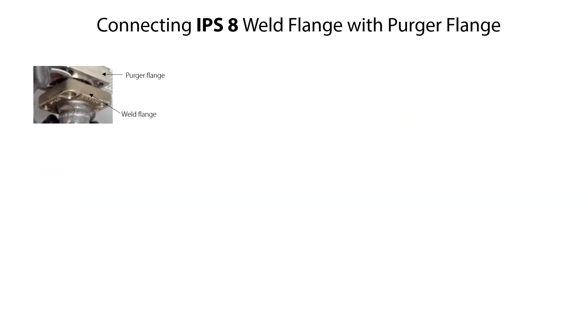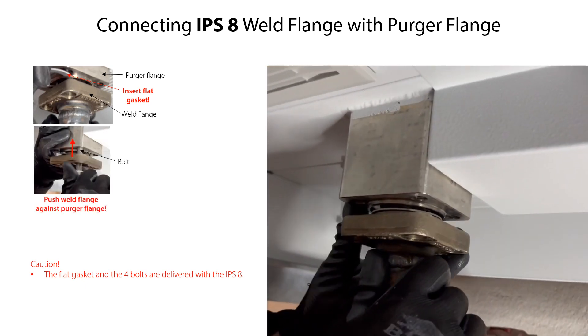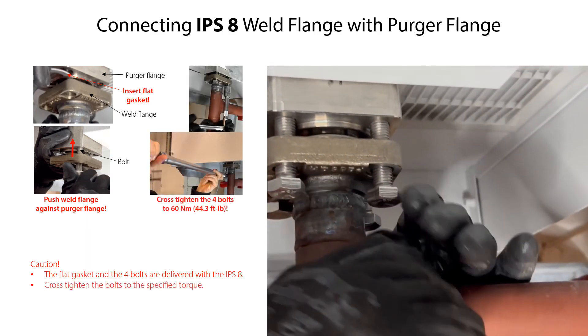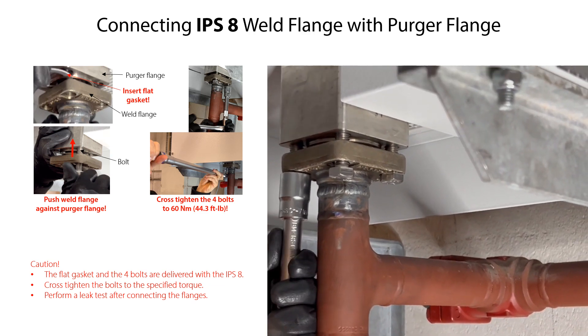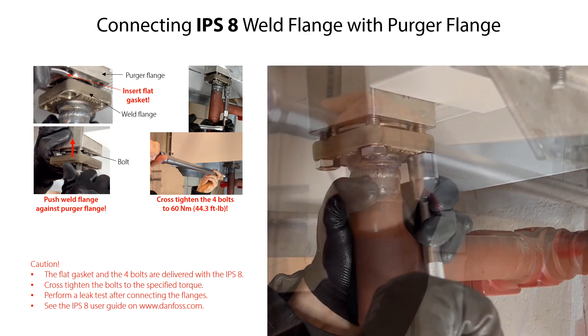We are now ready to connect the weld flange with the purger flange, using the flat gasket and the four bolts delivered with the IPS-8. Insert the flat gasket between the weld flange and the purger flange. Push the weld flange upwards against the purger flange while mounting the four bolts. Then cross tighten the four bolts to the specified torque. After connection of the flanges, perform a leak test according to legal requirements and given practice to ensure an airtight connection between the flanges.